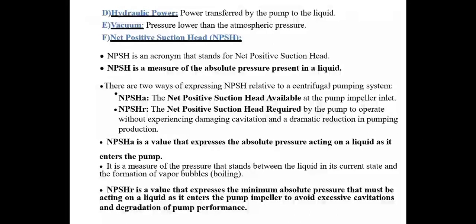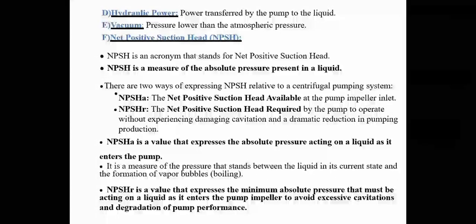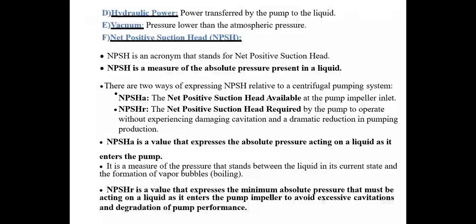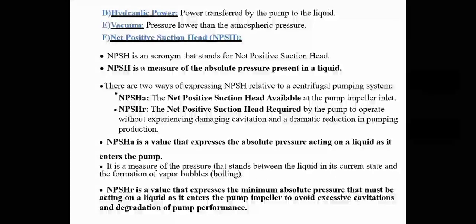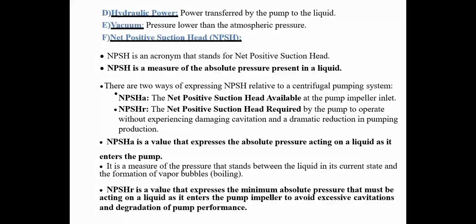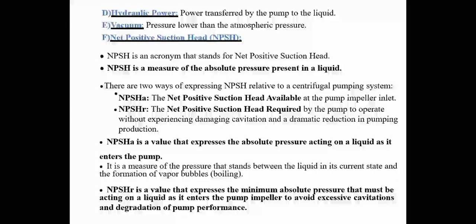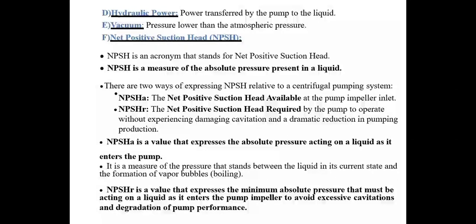If the NPSH available is less than the NPSH actually required by the pump, then there will be problems in the pump. You may have experienced some breaking sounds in the pump sometimes. That sound is caused by a process known as cavitation. Cavitation occurs when the NPSH available is less than the NPSH required for the pump.